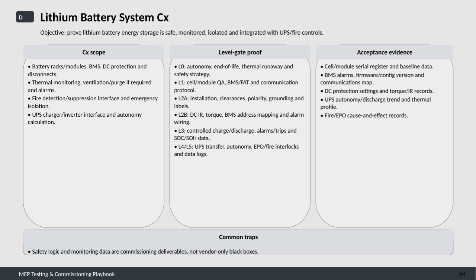At level 0, the focus is on autonomy, battery end-of-life considerations, thermal runaway prevention, and overall safety strategies. Level 1 covers quality assurance of cells and modules, factory acceptance tests of the BMS, and communication protocol verifications. The second level includes installation checks such as clearances, polarity verification, grounding, and labeling. Further, electrical tests like DC insulation resistance and torque checks, BMS address mapping, and alarm wiring are performed. Level 3 ensures controlled charge and discharge cycles, alarm responses, and state of charge and health data accuracy. The final levels, 4 and 5, verify UPS transfer functions, autonomy under load, emergency power off and fire interlocks, and thorough data logging.